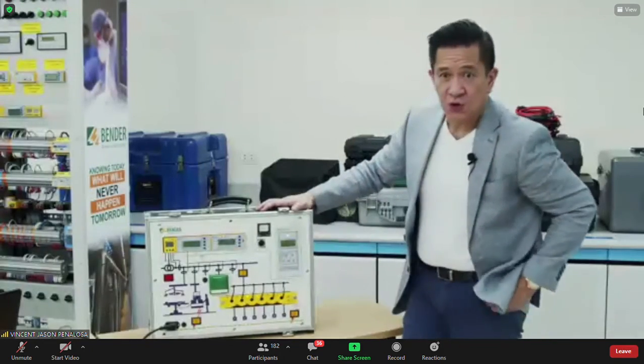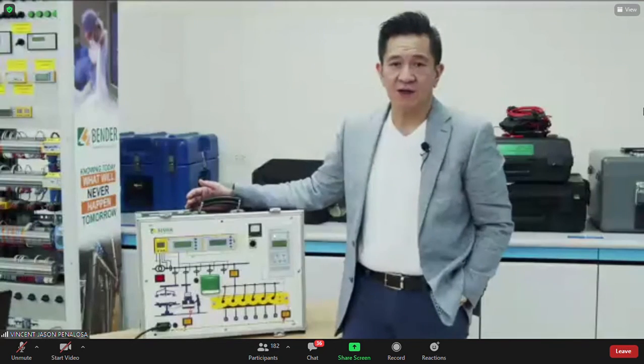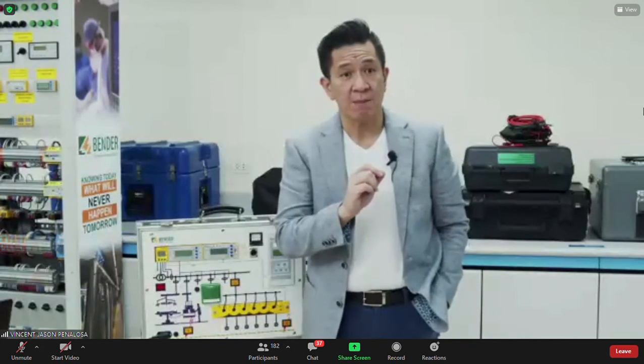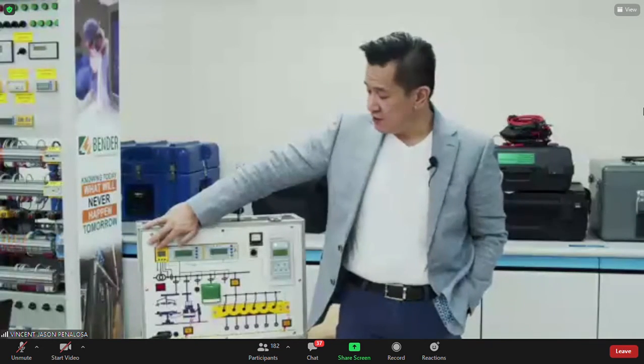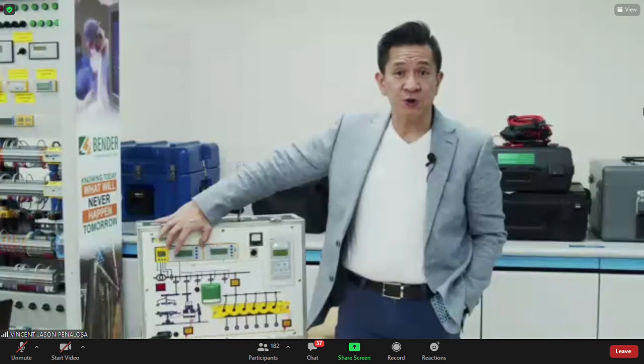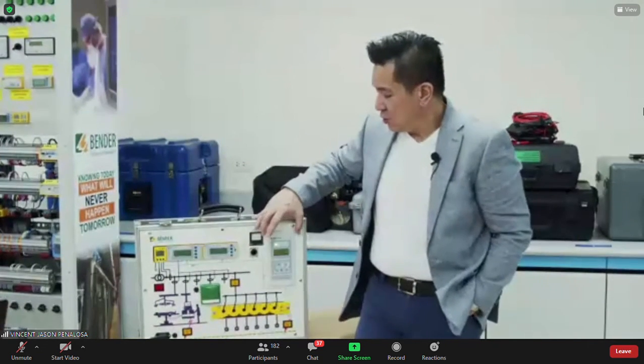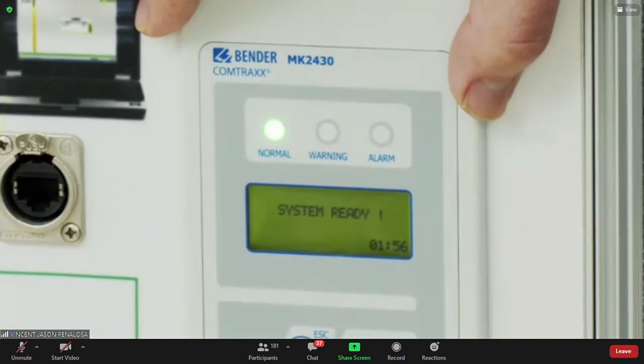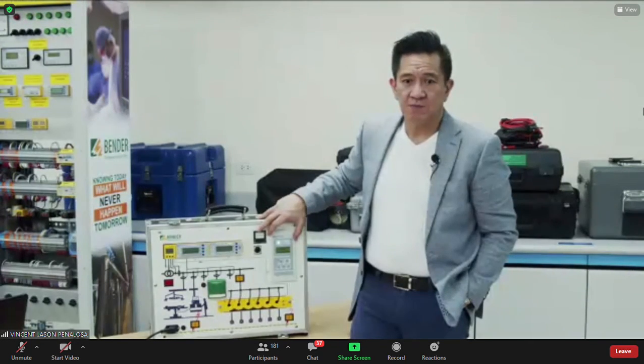All right. So once again, for an IEC compliant system, you will have a transformer that's no more than 10 kVA. There are specific requirements for those transformers, in terms of the inrush current and no load conditions. It's very specific, specifically made for medical applications. You will have an insulation monitoring device. The fault locator is optional. And then you will have the annunciator, kind of like a call button.